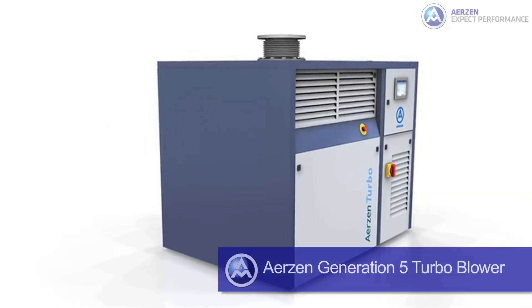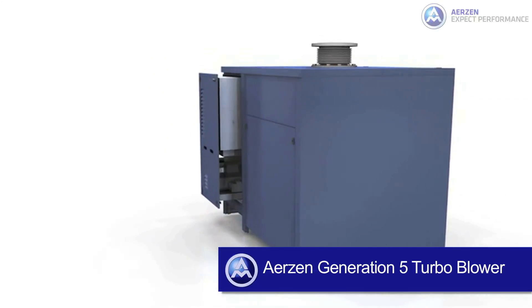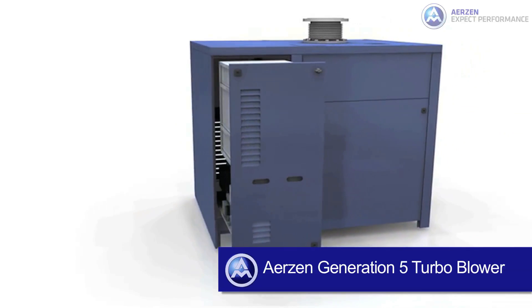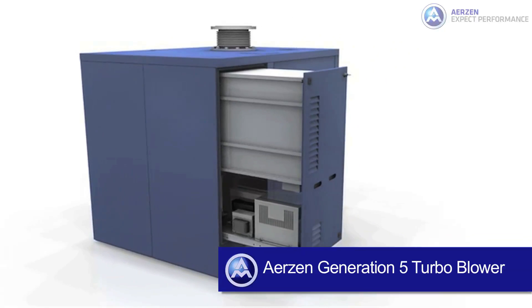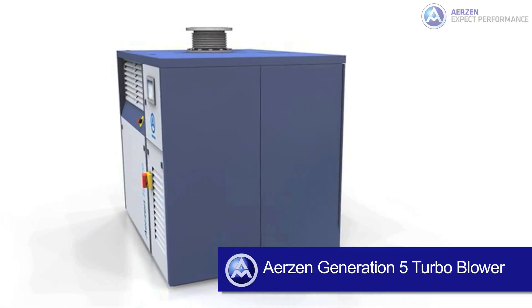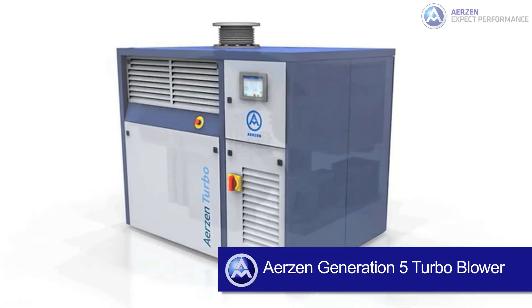Multiple valves precisely control the discharge pressure of each machine in operation. Additional capabilities include vibration and sound measurements. The Aerzen Generation 5 Turbo Blower is a single-stage, high-speed radial turbo blower designed to meet varying flow and pressure requirements. The package comes in a sound attenuation enclosure for easy machine access.